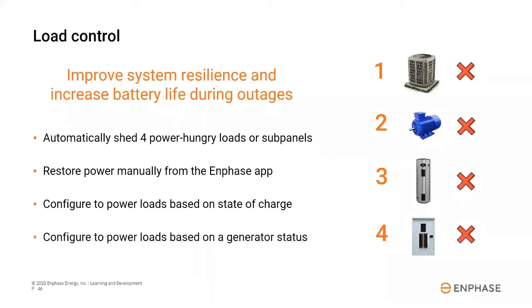And then lastly, it's also able to power loads based on the status of the generator. We're going to touch on generator support in a minute, but basically if the generator is running, you can set it up so that appliance will have power. And if the generator is not running and not helping supply power to the system, then power can be disconnected. So this is a feature that was added fairly recently to Enphase Storage. It does require some additional components and wiring, but the functionality and the control aspects, which are done through the Enlighten app, are all there and active.